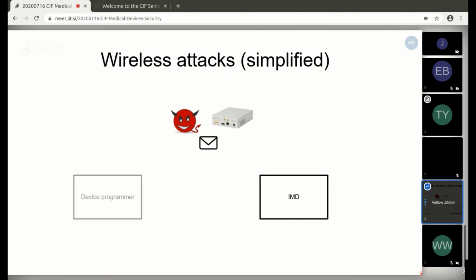Another thing that the adversaries could do would be to replay messages that were previously sent by legitimate device programmers, or create their own messages and send them to the implantable medical device. If the adversaries succeed in sending valid messages to the implantable medical device, they could, for example, deliver an electrical shock to the patient's heart, or give a high insulin dose to a patient. So these kinds of things. And obviously, these attacks can have devastating consequences for the patient, because they can potentially kill the patient or hurt them a lot.